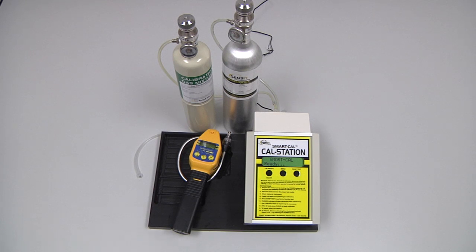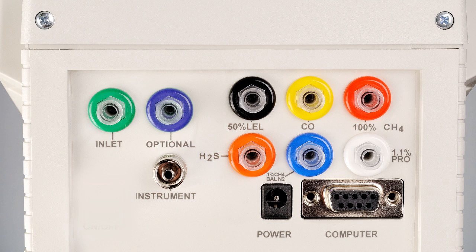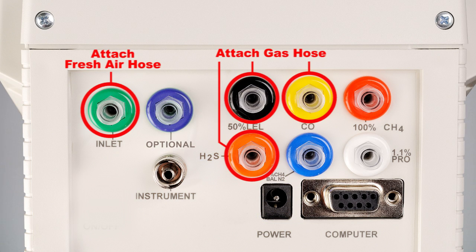To perform an automatic calibration of the Gold Basic, we will need the instrument itself, the cal station with instrument hose, and the calibration gas with regulators and cal adapters. This is a four gas instrument, so we will need a combination bottle of 50% LEL Methane and 100 ppm carbon monoxide, and a bottle of 25 ppm hydrogen sulfide.